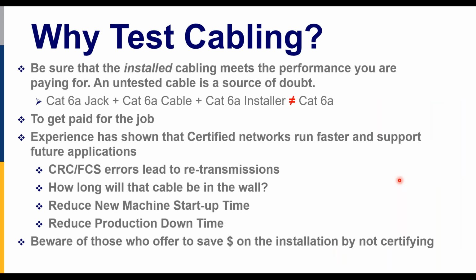While I'm up on my soapbox, why do we test the cabling? I'm using great jacks, great cable, I've got an installer with a piece of paper saying he went to one of your presentations, Jim. Isn't that enough? No — we want to make sure that when the cabling was installed, they didn't pull it too hard through the conduit, or lash it down with a cable tie too tight and crimp or bend the cable.